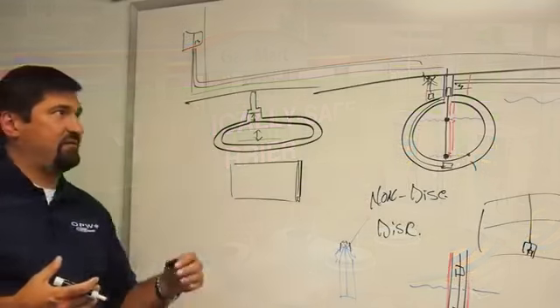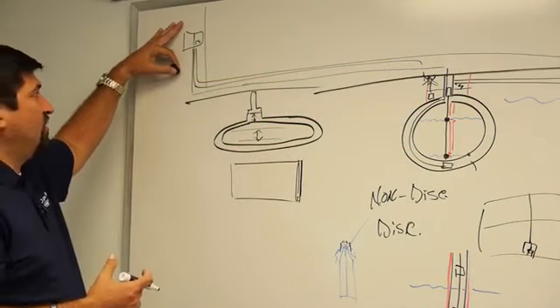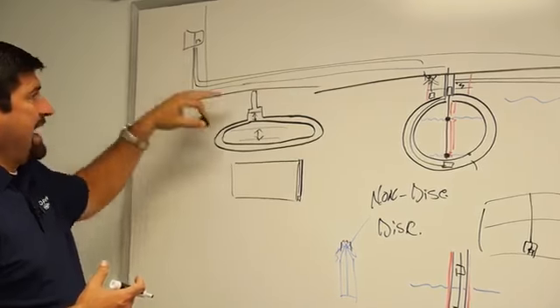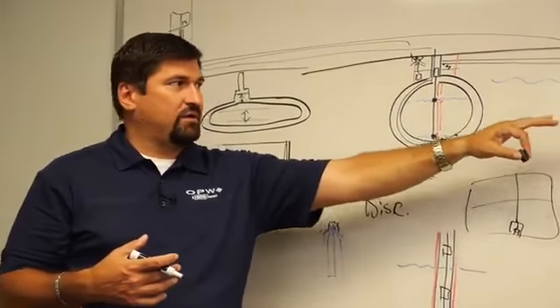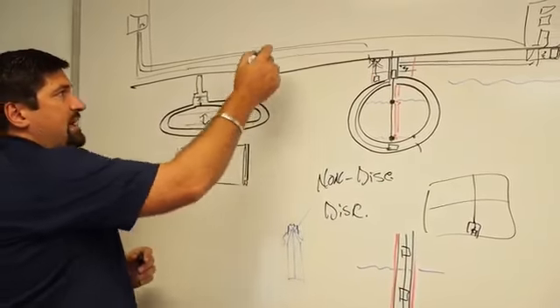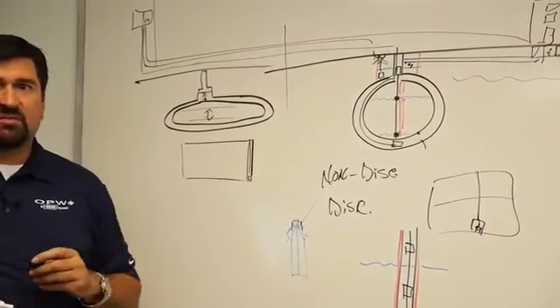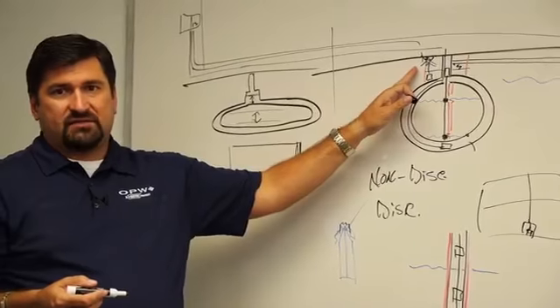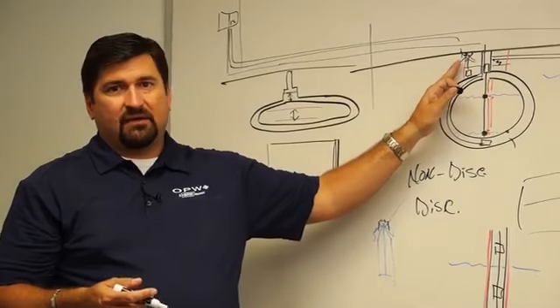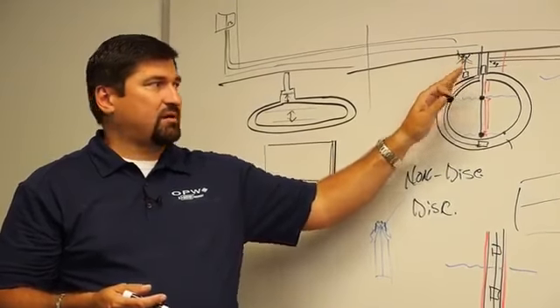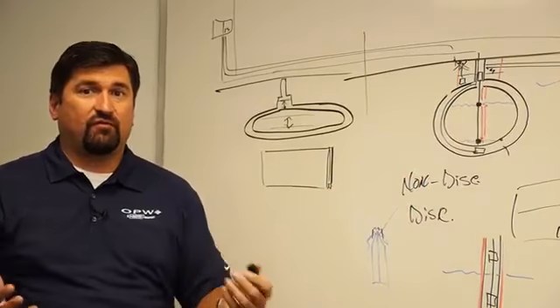That's your intrinsic safety, is that if I have the console, which is running high voltage, powering up the devices that are out in the field, that if for some reason somebody is saw cutting and cuts across my wires, at the point in which these devices are shorted out, I have the inability to create heat or spark to be able to ignite this fuel or the fuel vapors out in the field.